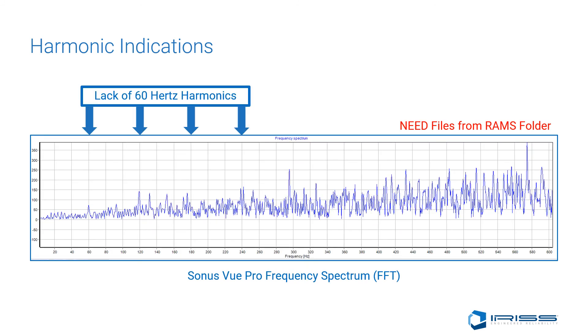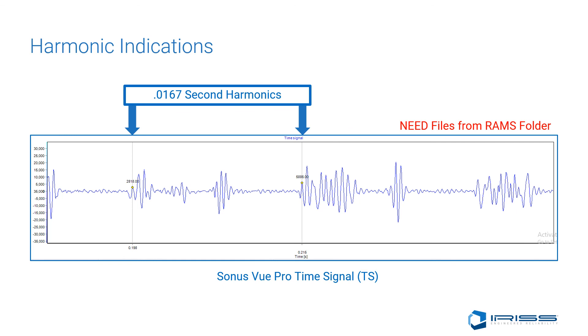In this example, the critical angle had not been achieved — hence the lack of rich 60 Hz harmonics: only a small indication at 60 Hz and another at 120 Hz before the values quickly disappear. Without sufficient signal strength for a rich 60 Hz harmonic pattern, these indicators still show that this event is treeing or tracking. Even without the critical angle, the time wave signal will still show the occurrence of 0.016 seconds, indicating the presence of an electrical anomaly. The consistent and even positive and negative amplitude scaling is a hallmark trait of treeing or tracking events.